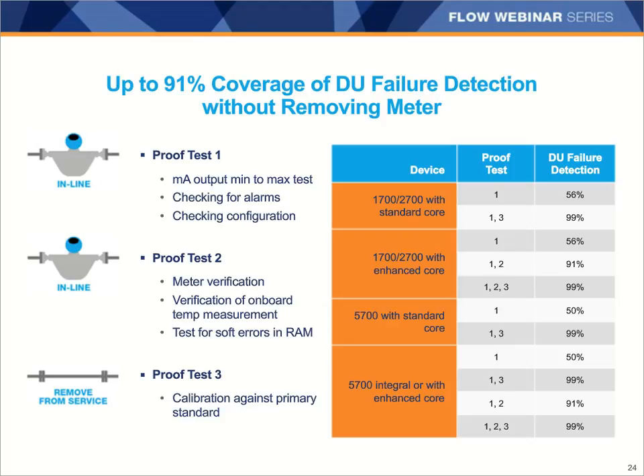But I do want you to keep in mind that this is because it has a higher SFF, and so there are actually fewer DU failures in the first place. So they both are good tests for the proof test 1, but it's going to cover only about half of your dangerous undetected faults. The best option, of course, to detect your DU failures is by removing the meter from the line and calibrating it against a primary standard. And this will cover about 99% of the DUs and is the full proof test.